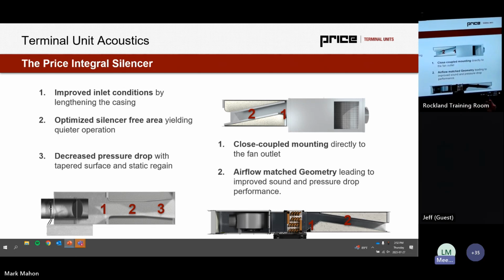What I mean by that is a 4-inch single duct doesn't get a 4-inch free inlet, free area silencer. A 5 with a 5, a 6 with a 6. We tested the whole fleet. We did CFD analysis to play with it to try to create as little turbulence as possible to maximize insertion loss and minimize generated noise. And then we also have this tapered surface, which some silencer manufacturers can't even manufacture or provide. And this helps provide some static regain. So it's really what we would quantify at Price like a medium velocity silencer.